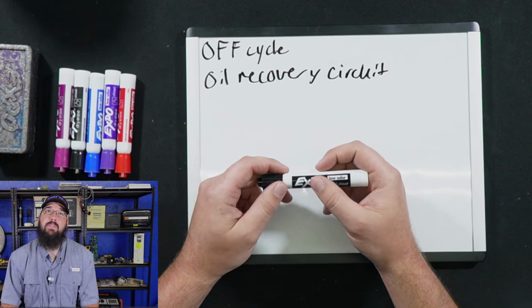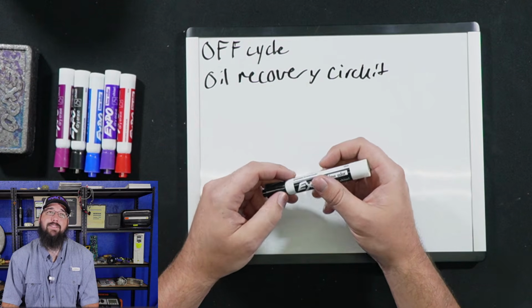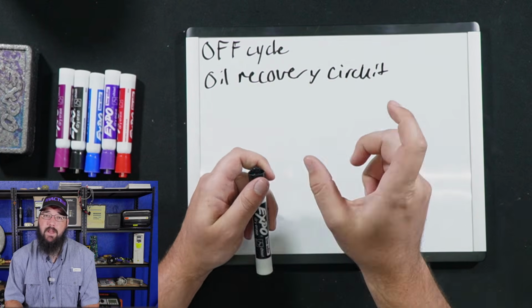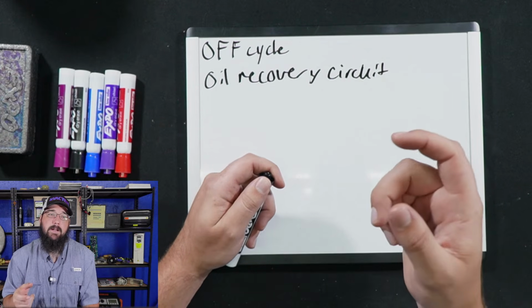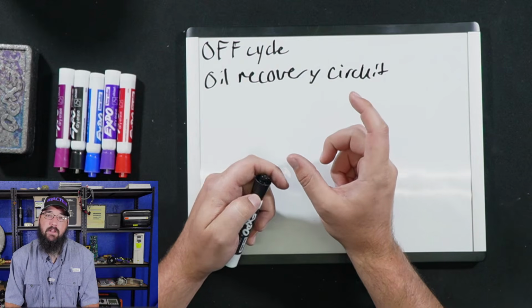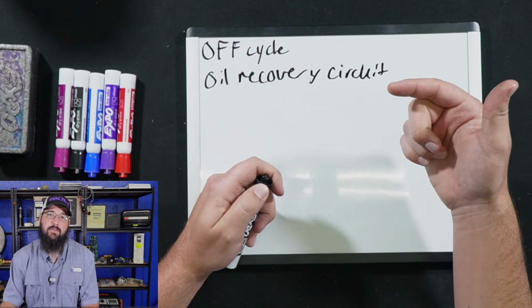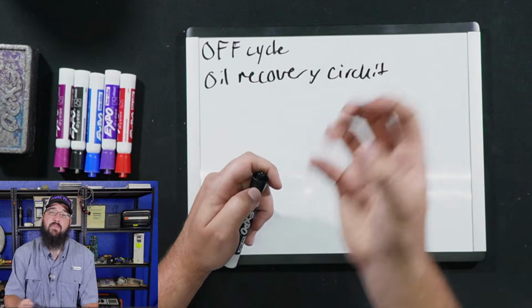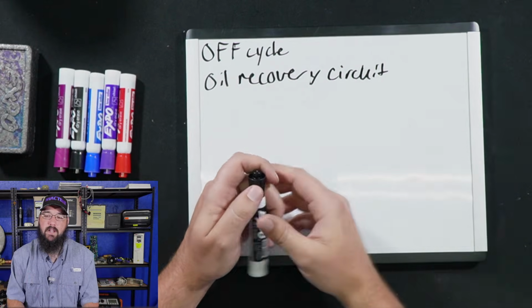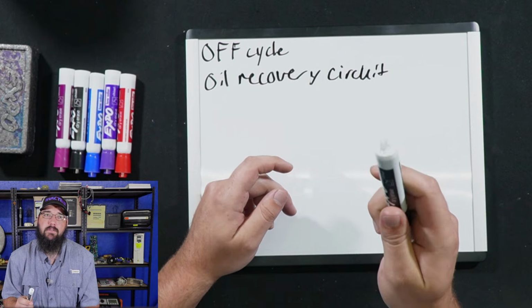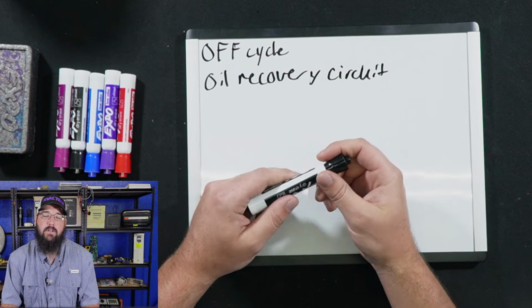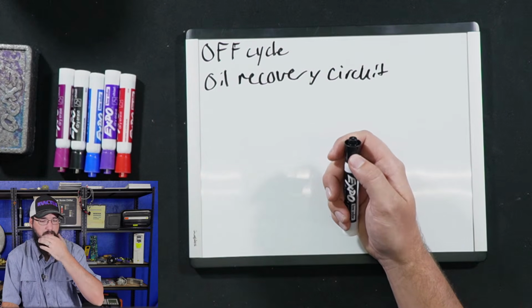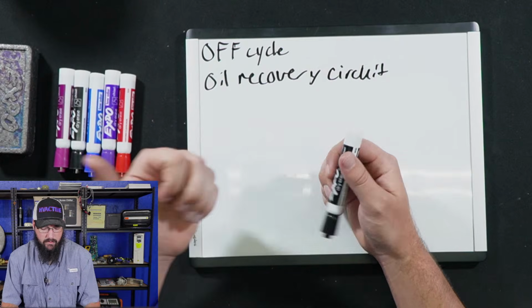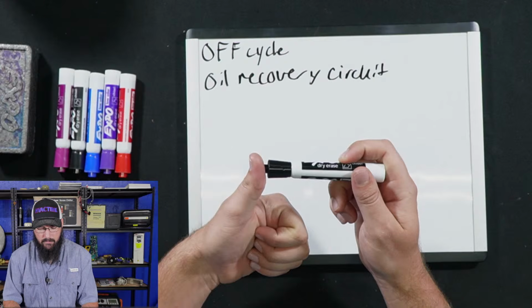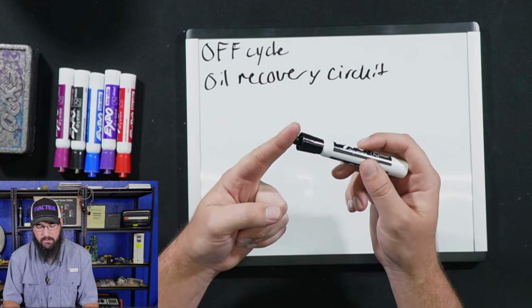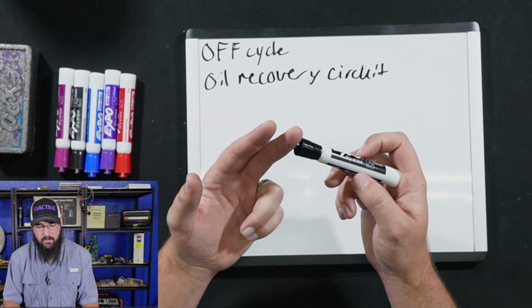If the eductor valve coming off the evaporator is not calibrated correctly, so with a lot of machines, we have to manually set that valve. It's not just to leave it wide open. But if it's closed off too much and you don't have it open far enough, then that can cause the oil to stack because it's just not pulling enough volume off and sending that back to the sump. So it could be a calibration issue for your eductor return line coming back into your oil reservoir. Let's see, how many other scenarios? We talked about low, high level, filter, the valve calibration.